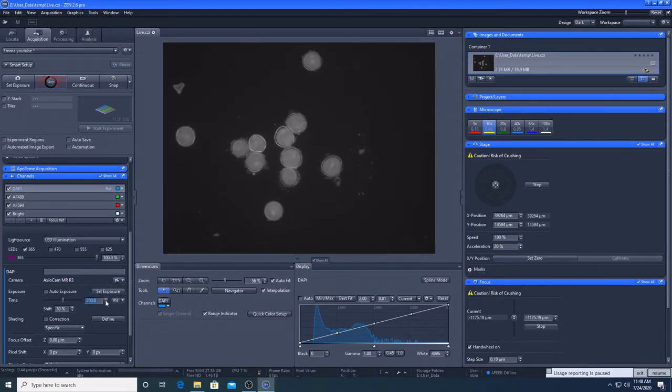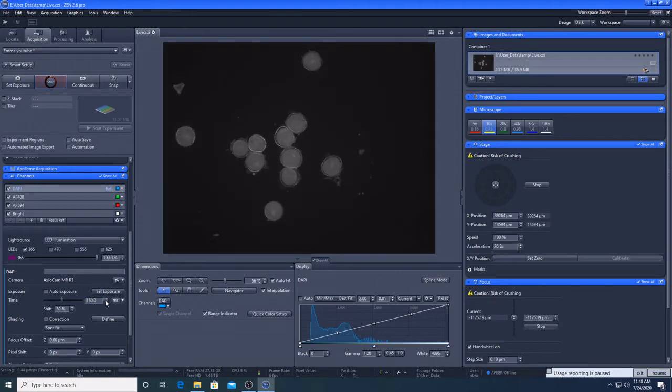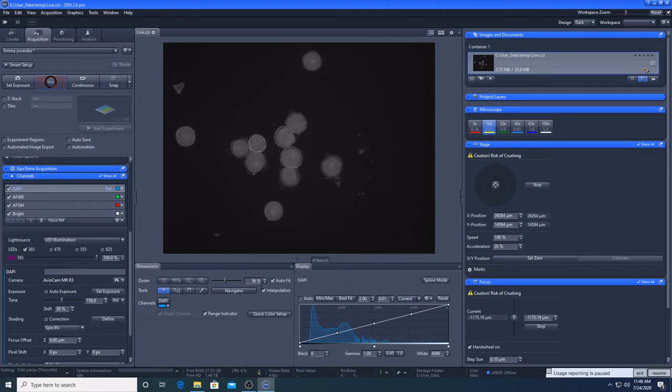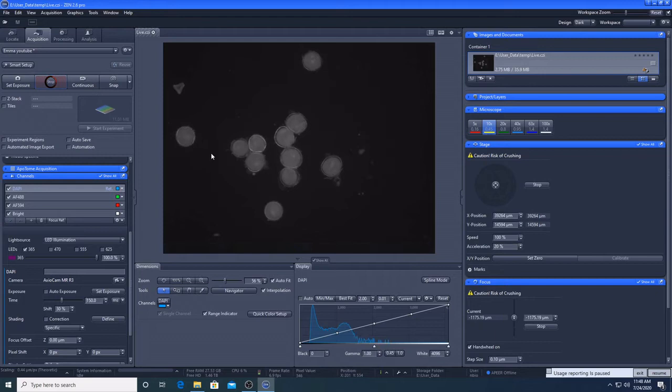The benefits of keeping the exposure time to a minimum are reducing the effects of bleaching, reducing overall imaging time, which is something to keep in mind for tiling and z-stacks, which we will come back to later, and for if you are intending to do intensity comparisons using the same settings, it gives you more wiggle room in the measurable zone if subsequent samples are brighter. We also recommend that when you are creating your settings that you start with what you anticipate to be your brightest sample.